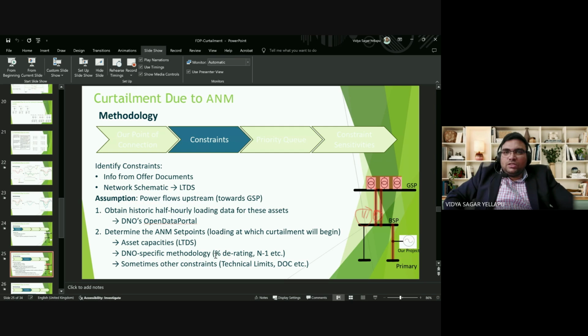Then there is the DNO-specific methodology, that is, how the DNO operates the active network management scheme. Is it based on 95% derating of any asset? That means if 95% of the rating of any asset is reached, generators are given signals so that they have to reduce their generation. Is it based on N-1 or N-2 outages, etc.? All this information is given in the DNO-specific methodology. There are other constraints such as reverse power flow constraints, directional overcurrent limit constraints, etc. Those are to be understood.